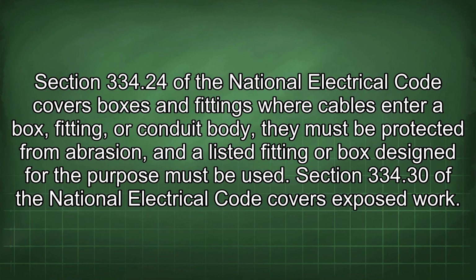Section 334.24 of the National Electrical Code covers boxes and fittings where cables enter a box, fitting, or conduit body. They must be protected from abrasion, and a listed fitting or box designed for the purpose must be used.